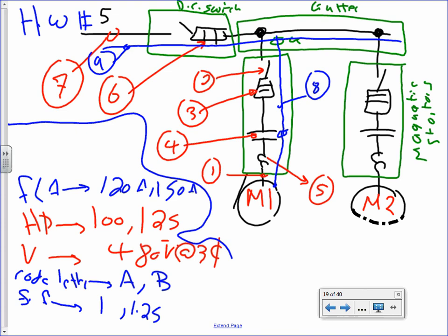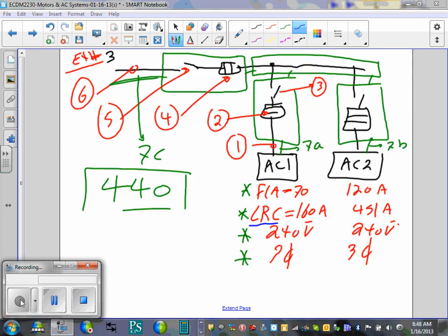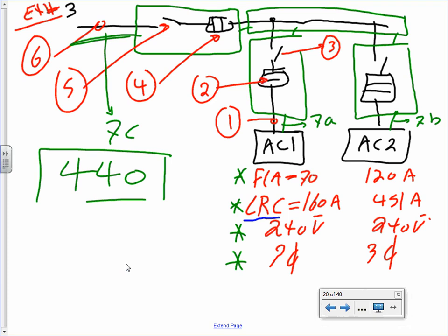Okay, 5 minutes, and I want to do one more example, guys, except these are HVAC equipment, like chillers and so forth, specialty. This example is extremely similar, except it's HVAC equipment. When I talk about HVAC equipment, Article 440 of the NEC code book deals with it. The only difference between HVAC equipment and a motor is that they have some type of refrigeration cycle. They have a compressor. If the equipment has a compressor, it has hermetically sealed motors, which deal with the refrigeration cycle. If it has some type of action with the refrigeration cycle, you have to move directly into Article 440.